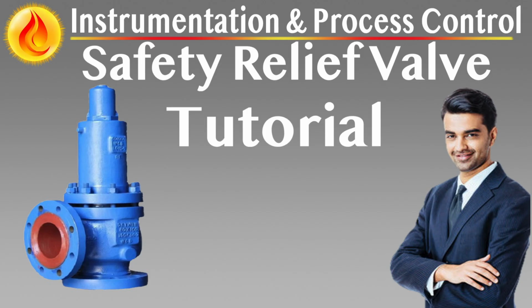Air-assisted relief valves are a hybrid design that combines the simplicity of spring-loaded valves with the precision of instrumentation-assisted actuation. These valves incorporate a pneumatic actuator, typically a diaphragm or piston type, that applies additional closing force near the valve's set pressure. This supplemental load increases sealing reliability, reduces premature lift, and allows the set pressure to be approached more closely during normal operations. Used selectively in critical services, air-assisted valves are especially valuable in tight margin systems where the difference between the maximum operating pressure, MOP, and the valve set pressure is limited to as little as 5%.